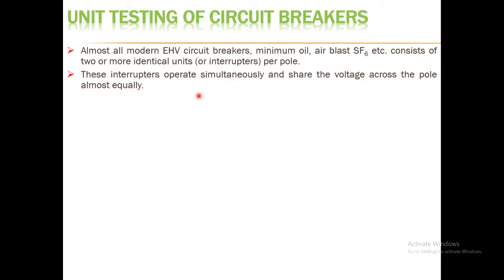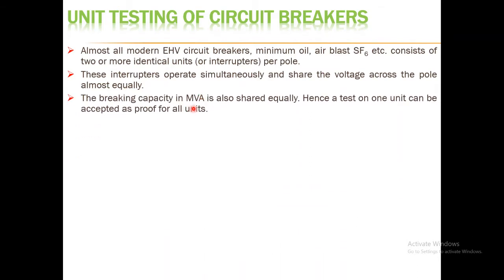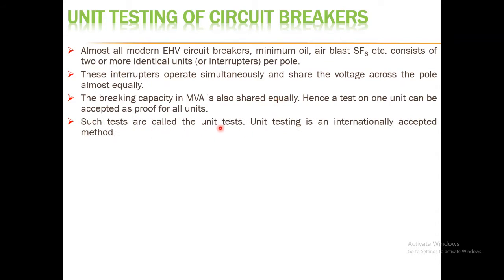The breaking capacity, expressed in MVA, is shared equally by all interrupters. So the test on one unit can be accepted as proof for all units. During unit testing, only one unit is put under test while the others are isolated — meaning grounded. The test is performed only on one pole and based on that result the others can be accepted. Such tests are called unit tests, and unit testing is an internationally accepted method.